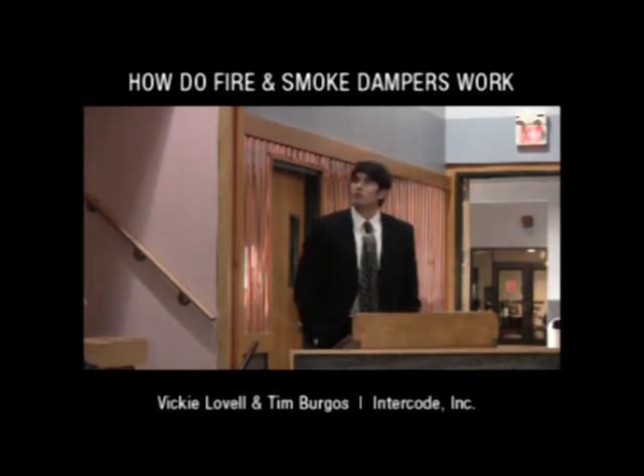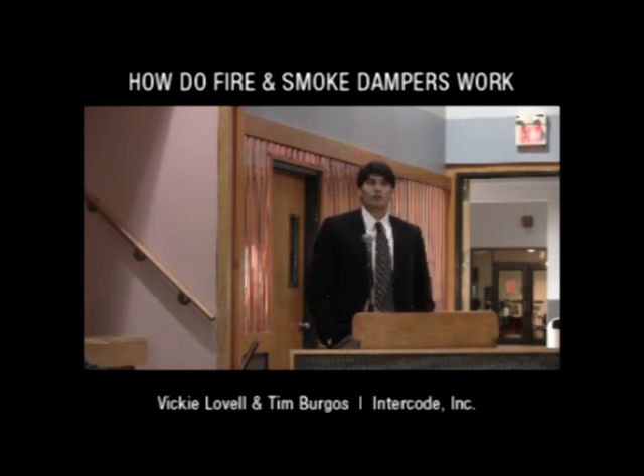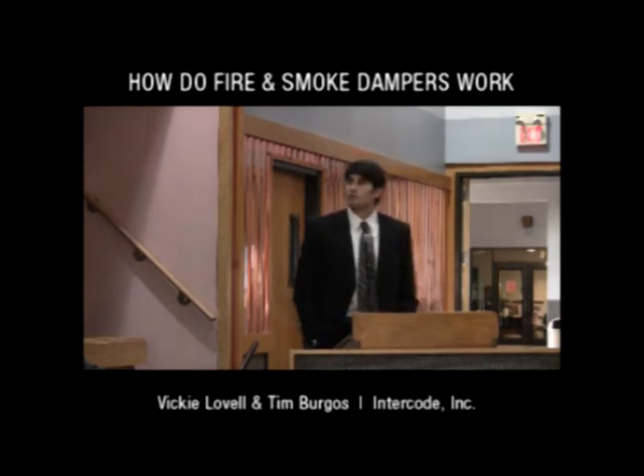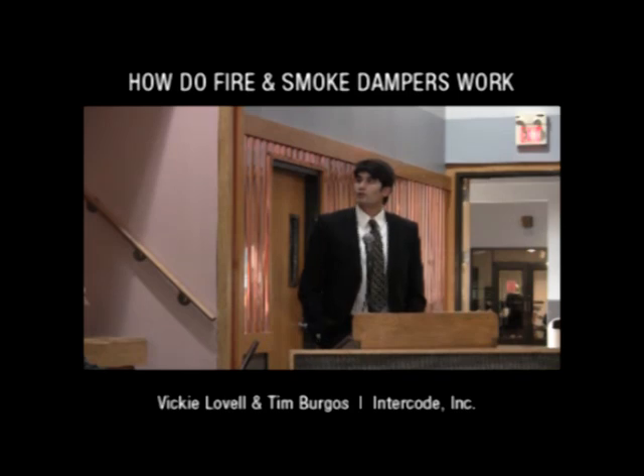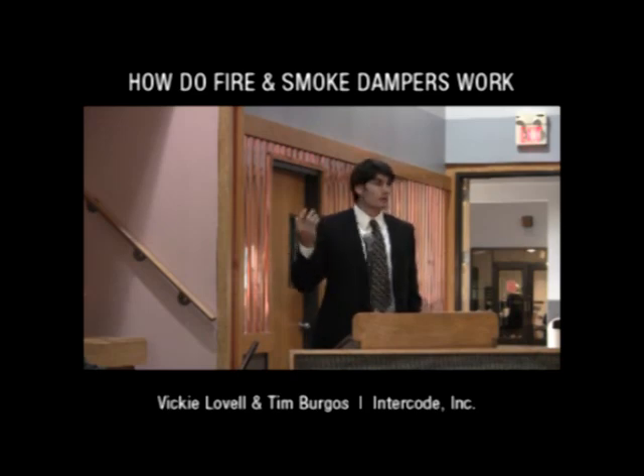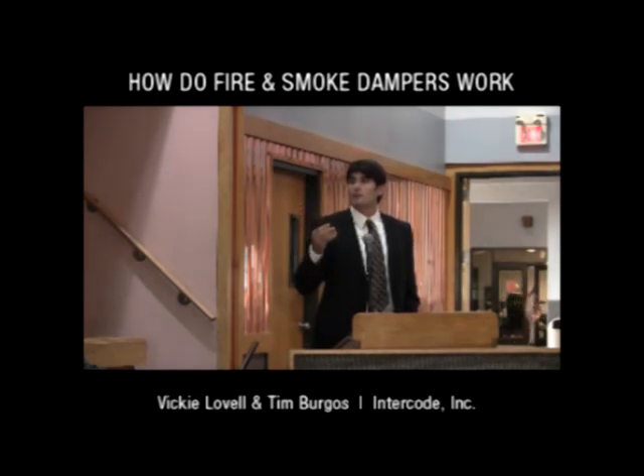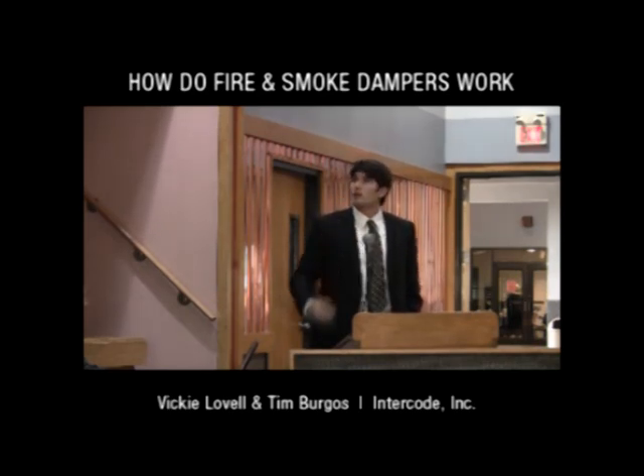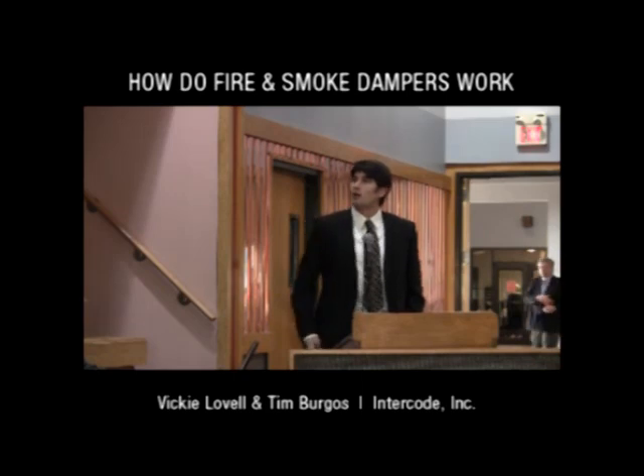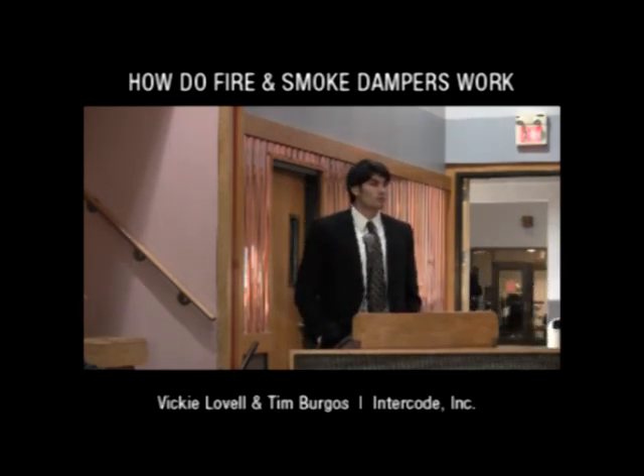The other type of damper is a motor or actuator operated damper. You'll see these are used for smoke dampers, most combination fire smoke dampers, and also some fire-rated dampers, fire dampers. How these work is there's a motor that will either open or close depending on the situation. For a smoke damper, there's a smoke detector that feeds a signal to the smoke damper, and when it detects smoke, it will command the actuator to close the damper, sealing off the smoke from going through the HVAC system. A combination fire smoke damper also works in the same way. When fire and or smoke is detected, a signal will be sent to the actuator to close the damper, also sealing off the rest of the building from the fire and smoke that is being spread through the HVAC system.